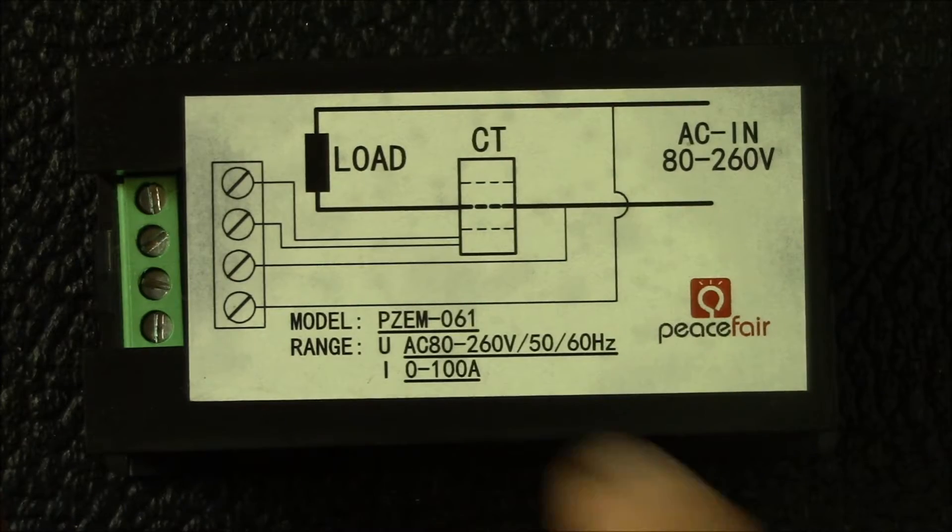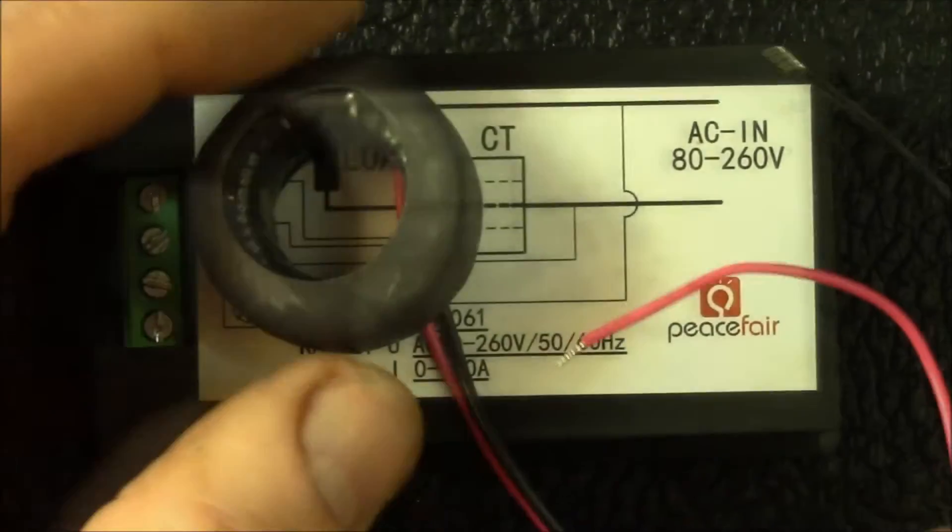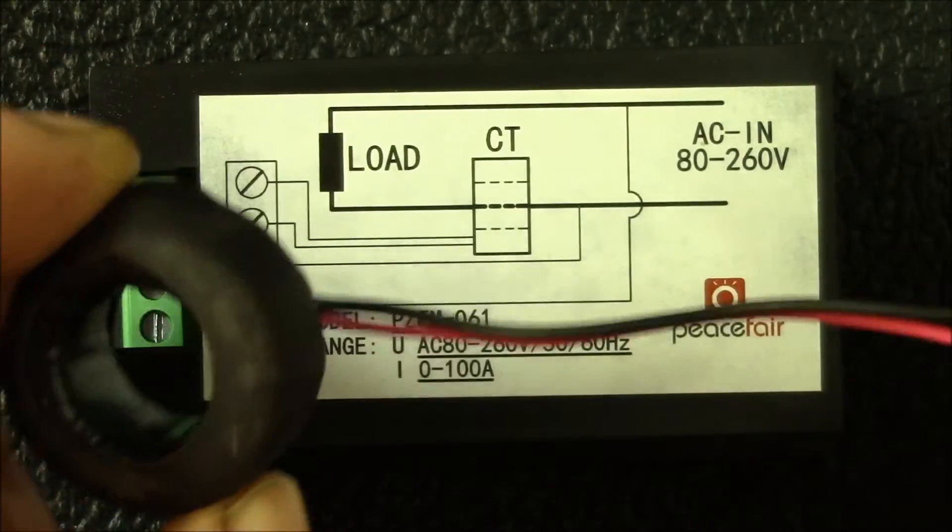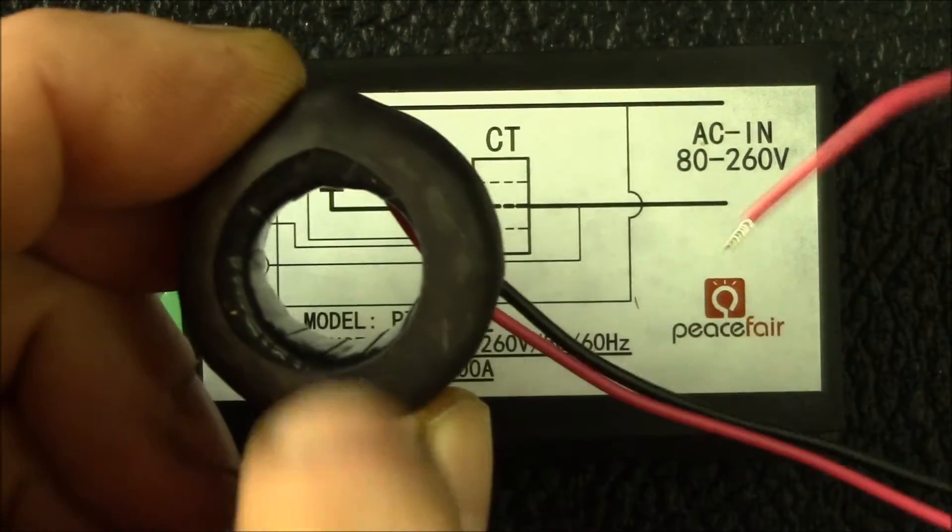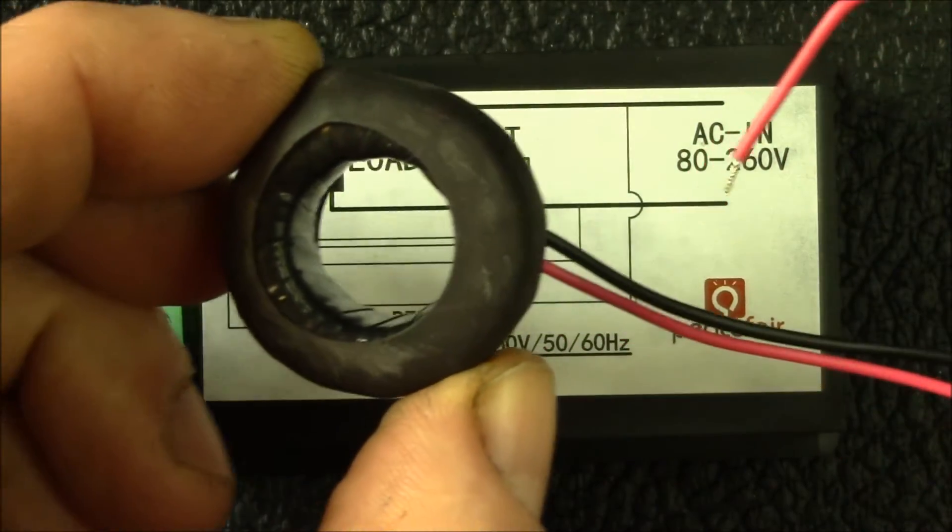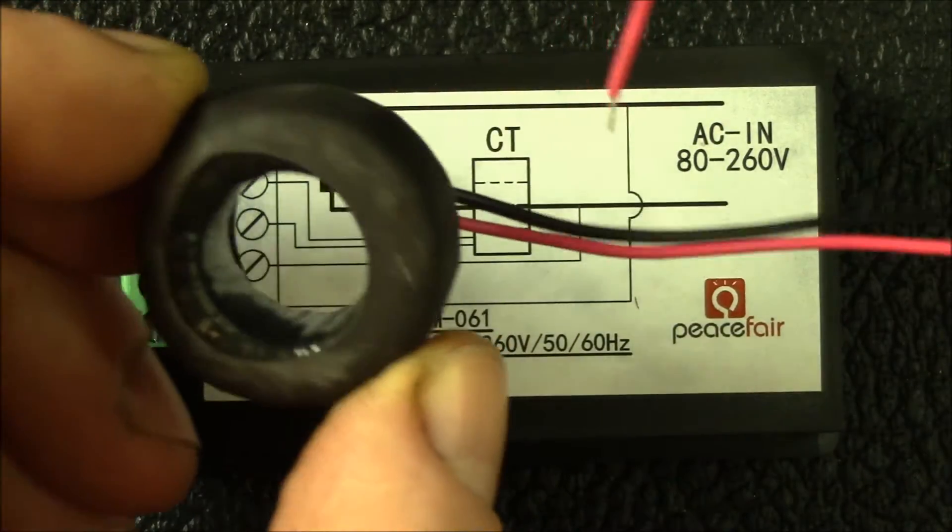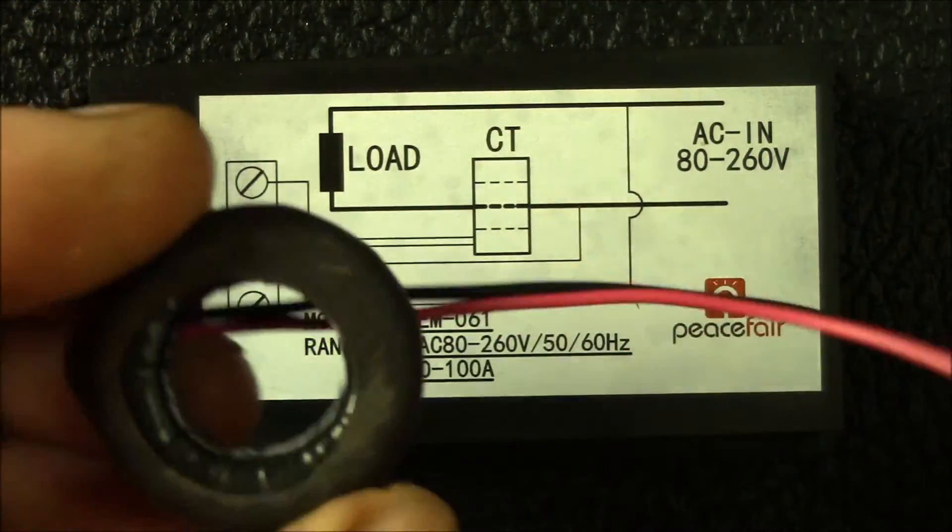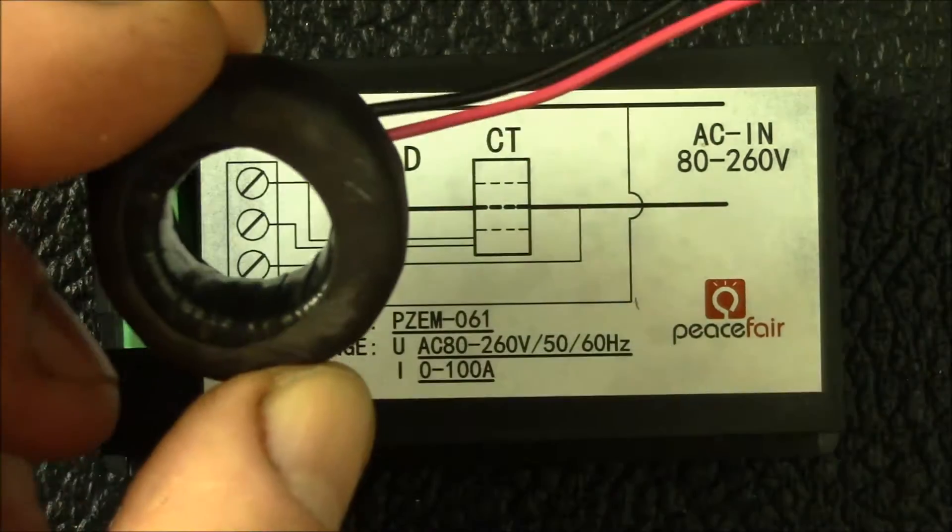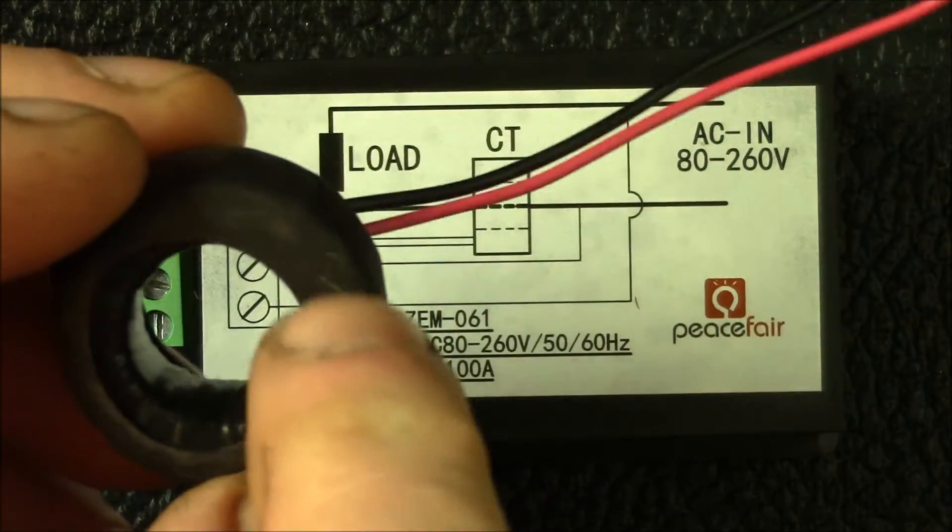Here's the AC current transformer. This is what senses your load current. It's about a 16 millimeter or 5/8 inch diameter inside the current transformer, so it would fit around a pretty large size cable. Apparently it's rated at 1000 to 1.